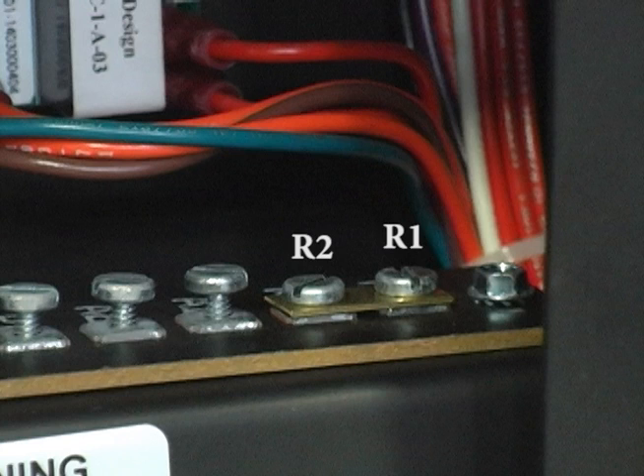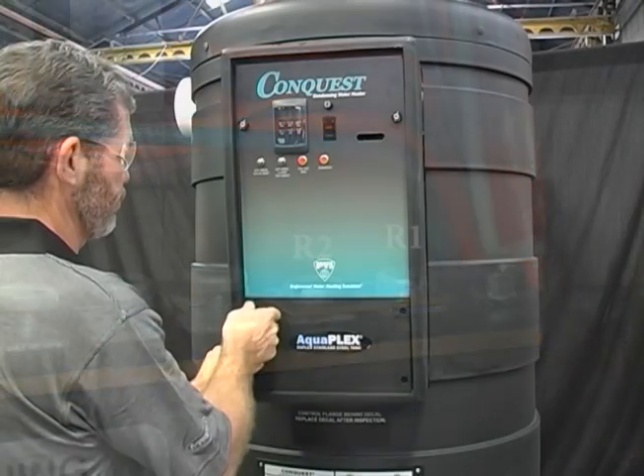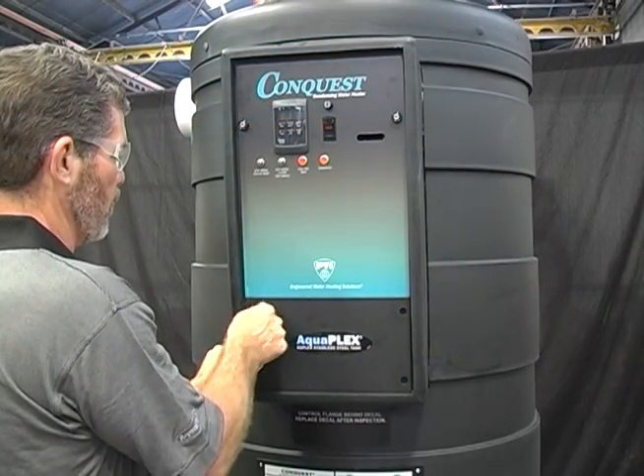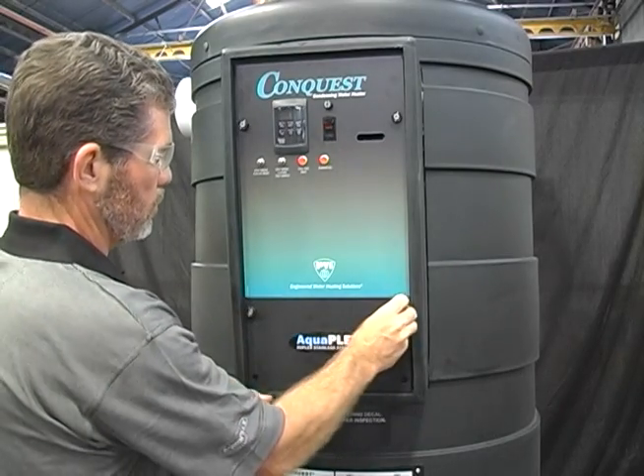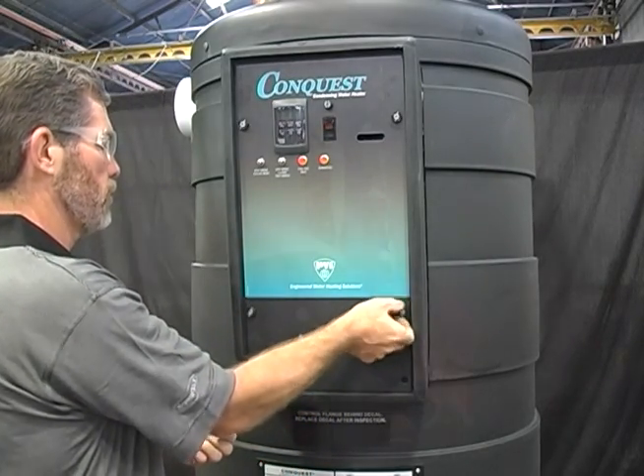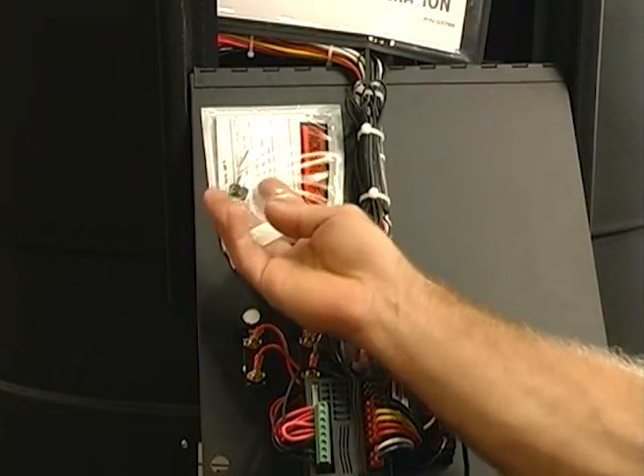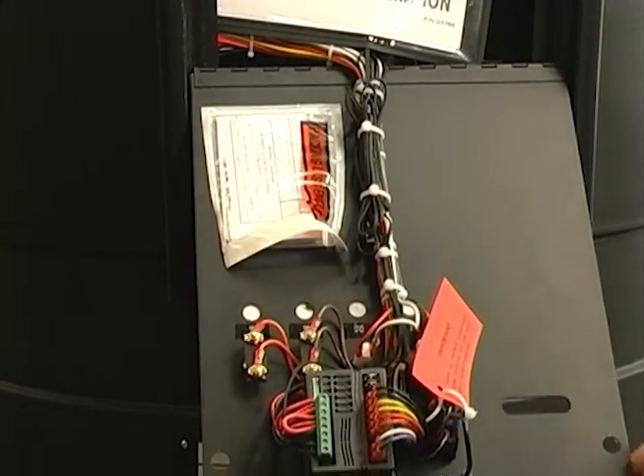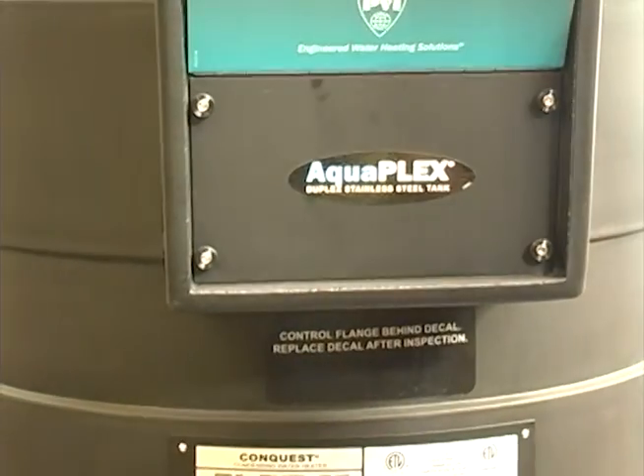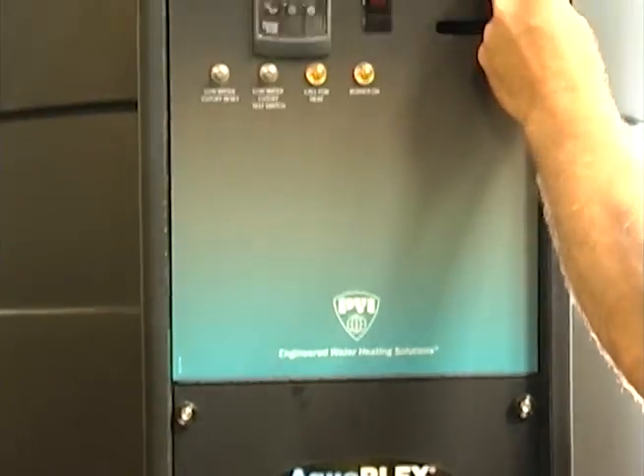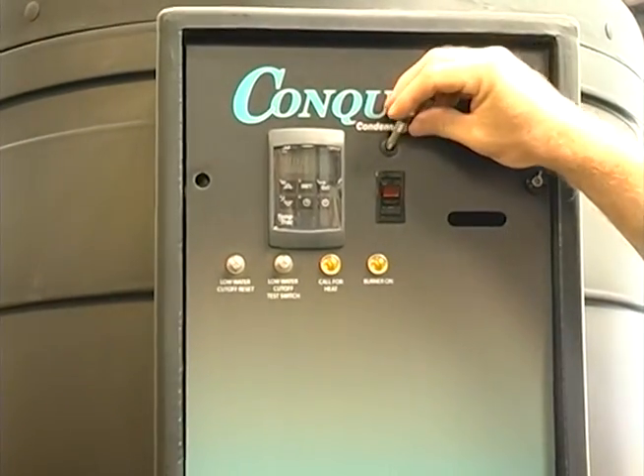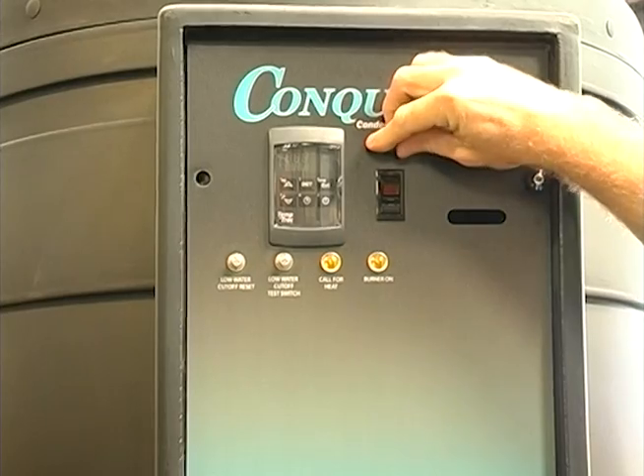When first starting up the water heater, the heater must be isolated from any remote controlling device. These wires must be removed and the terminals must be jumpered. Remember to reconnect the remote wires after startup is complete. Close and secure the lower control enclosure cover with the panel screws. This must be done before opening the upper control enclosure cover. While doing this, check to see if the control circuit fuse is installed on the face of the control panel. If not, the fuse is located on the inside of the upper cover in a plastic bag taped to the inside of the panel. Install the fuse.